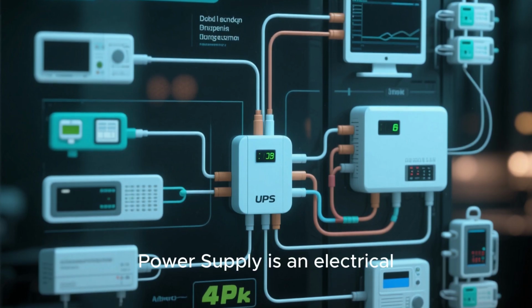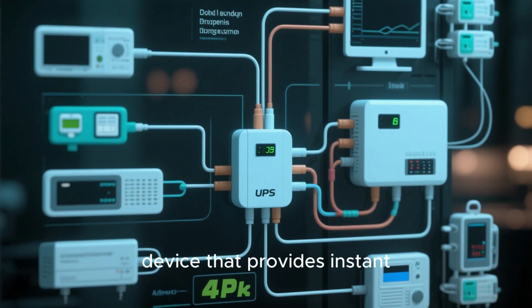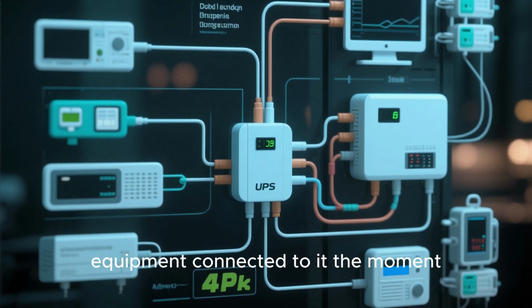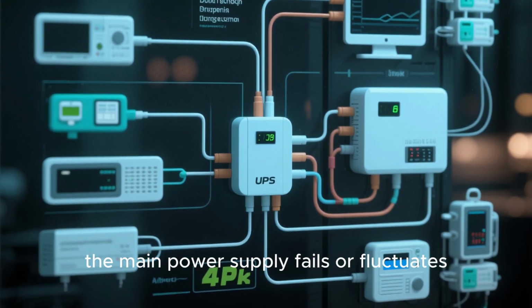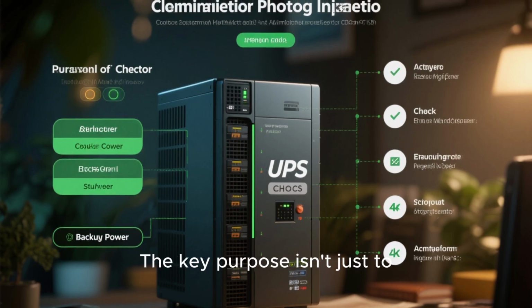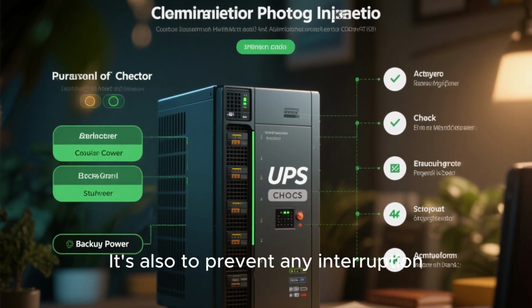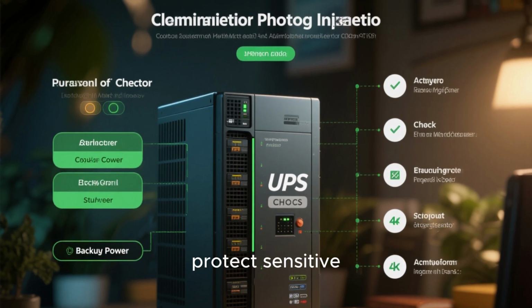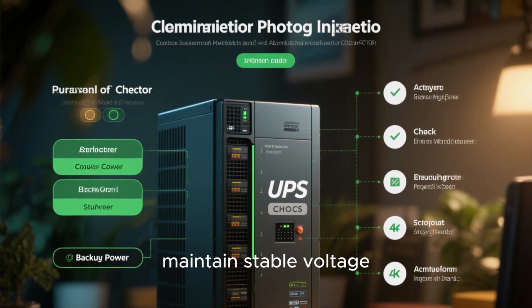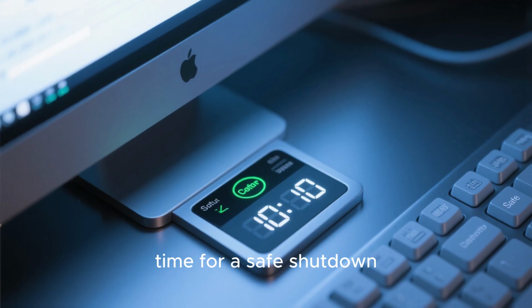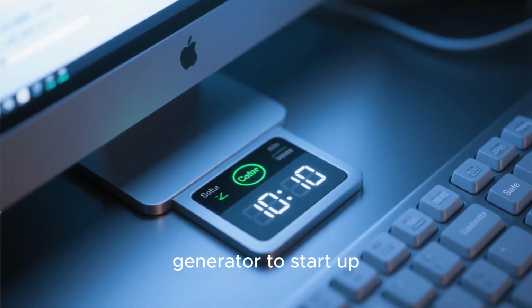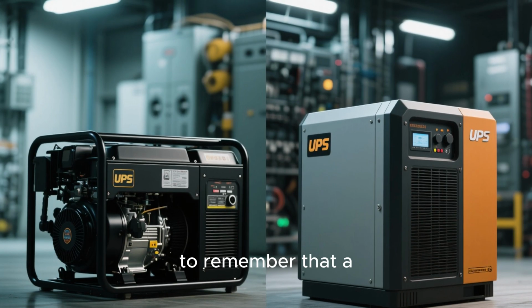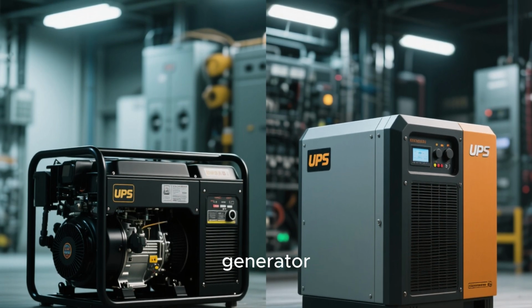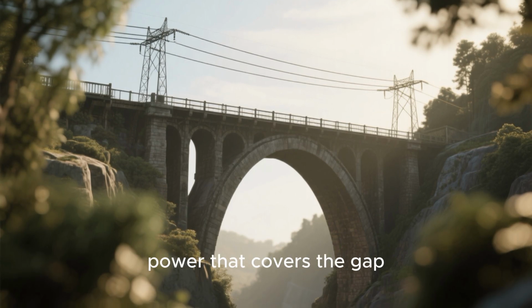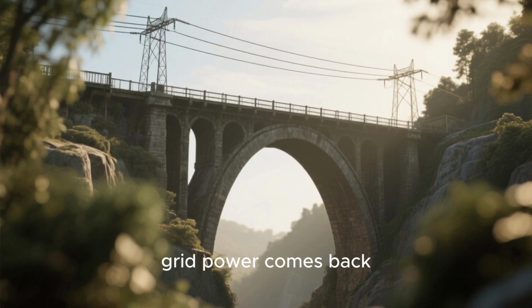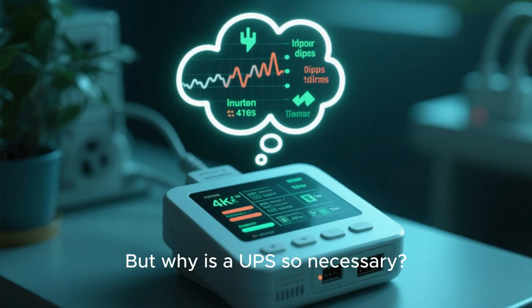An uninterruptible power supply is an electrical device that provides instant, clean backup power to the equipment connected to it the moment the main power supply fails or fluctuates. The key purpose isn't just to provide backup power. It's also to prevent any interruption, protect sensitive electronics from damage, maintain stable voltage, and give you enough time for a safe shutdown or for a backup generator to start up. It's really important to remember that a UPS does not replace a generator. It is the immediate bridge of power that covers the gap until the generator kicks in or the grid power comes back. But why is a UPS so necessary?